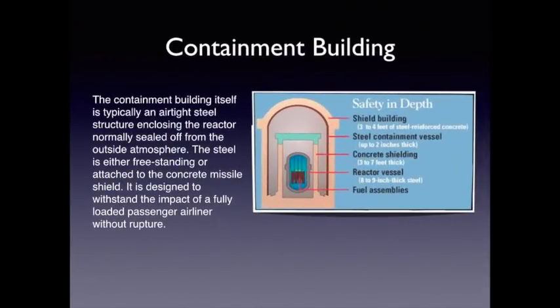The containment building is typically an airtight steel structure enclosing the reactor, normally sealed off from the outside atmosphere. The steel is either freestanding or attached to a concrete missile shield. It is designed to fully withstand the impact of a loaded passenger airliner without rupture or exposing the reactor core to the environment. The shield building is anywhere from 3 to 4 feet of steel-reinforced concrete, the steel containment vessel itself is 2 inches of thick metal plate, inside that there is up to 7 feet of concrete shielding, and the reactor vessel itself has 8 to 9 inch thick steel plating.